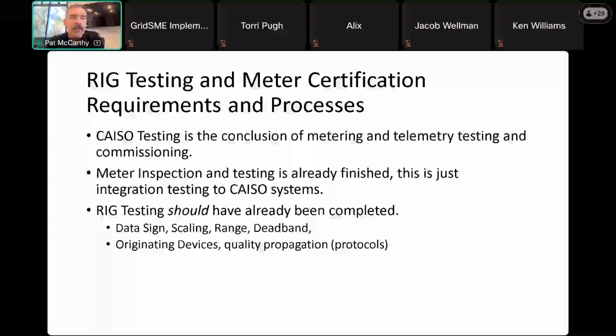This is the conclusion of your metering, testing, and commissioning activity. Again, CAISO doesn't want bench testing — they want to test the system that's actually going to be operating. They don't want to test your facility separately from how it's going to operate in their system. All of your inspections and local testing should be complete.